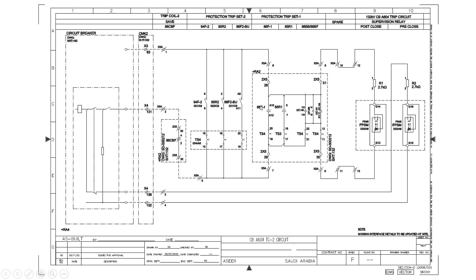When 86F1 or 86F2 is operated, the positive will continuously come to the tripping coil. But whenever the CBF relay operates — which is clearly the circuit breaker failure case since the breaker is not opening — the CBF NC contact will open, blocking the positive up to terminal 2X532 so it will not go out to 2X533 or X5A2. The trip coil will not get a continuous positive and it will be safe. This is the Trip Coil 2 save scheme.